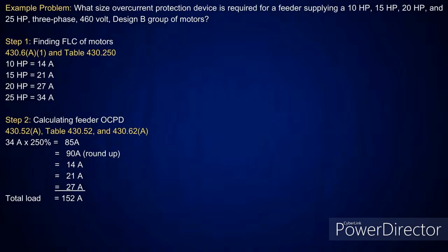Now, just like we did when we were doing the conductors, you're going to take the largest motor at, in this case, since we're doing an inverse time circuit breaker, you're going to look at table 430.52, and it's going to tell you to take it at 250%.